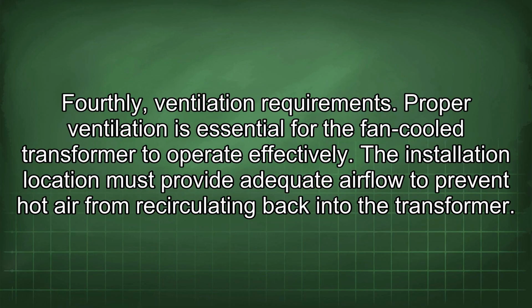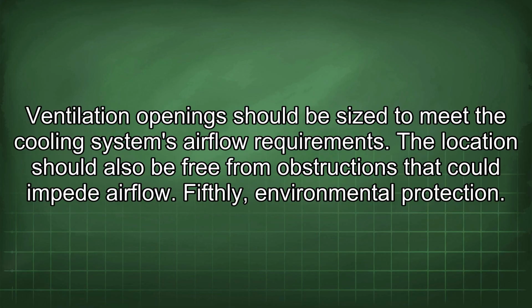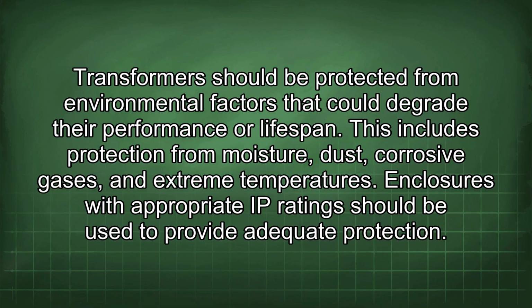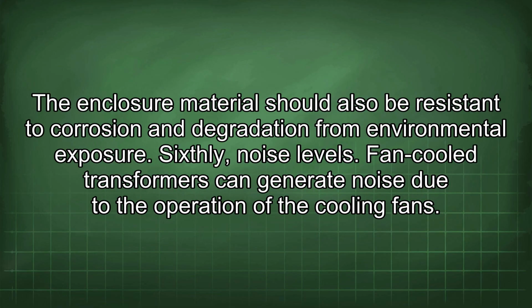Fourthly, ventilation requirements. Proper ventilation is essential for the fan-cooled transformer to operate effectively. The installation location must provide adequate airflow to prevent hot air from recirculating back into the transformer. Ventilation openings should be sized to meet the cooling system's airflow requirements. The location should also be free from obstructions that could impede airflow. Fifthly, environmental protection. Transformers should be protected from environmental factors that could degrade their performance or lifespan. This includes protection from moisture, dust, corrosive gases, and extreme temperatures. Enclosures with appropriate IP ratings should be used to provide adequate protection. The enclosure material should also be resistant to corrosion and degradation from environmental exposure.